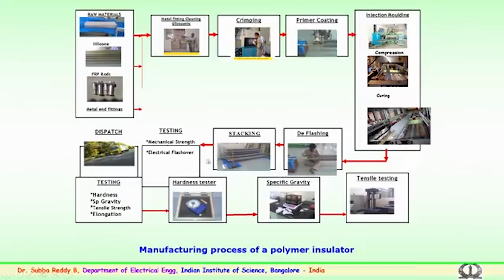Then after stacking, it is sent for regular testing, both mechanical and electrical. The testing includes, apart from electrical and mechanical, hardness, specific gravity, tensile strength and elongation for the rubber. These are material-related tests carried out using a hardness tester, a specific gravity meter or tensile strength machines in the factory. The entire process of manufacturing a polymer or silicon rubber insulator takes anywhere between 4 to 5 hours, whereas ceramic or porcelain used to take 24 days.